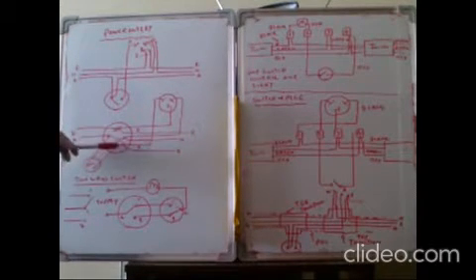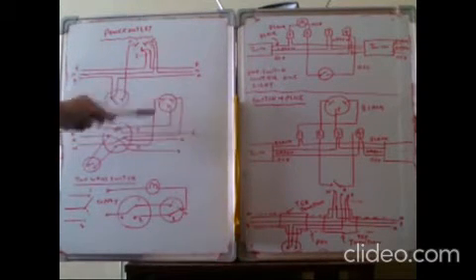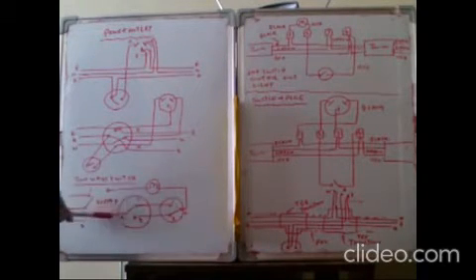We can also connect a switch with a power outlet. The active wire goes through a switch, then to the socket outlet. The neutral wire and earth wire connect directly. For the two-way switch system, two switches can control one light: turn on at one switch, turn off at the other. Each two-way switch has terminal 1, terminal 2, and a common terminal — terminal 1 and 2 connect between the switches, and the common connects to the incoming and outgoing lines.